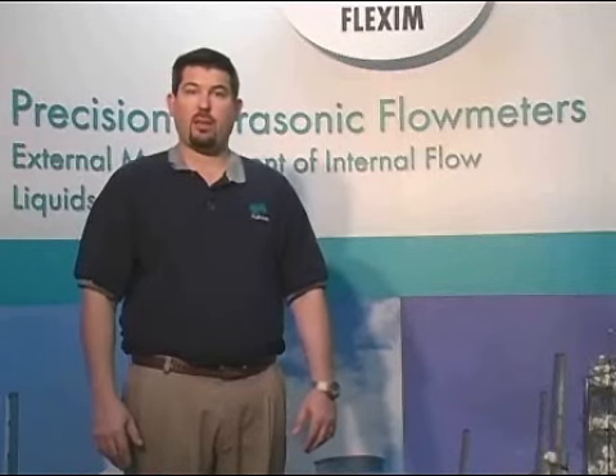Today we covered the basics of how to configure an ADM 7X07 energy meter. We talked about how our temperature probes were installed, how our menu system is laid out, and how to navigate through it. We talked about how to tell the meter what type of fluid and pipe you're measuring on. And then we went into some detail on how to configure process inputs and link temperatures, as well as how to set up outputs like a 4 to 20. After that, we went through the process of actually starting a measurement. And lastly, we talked about how to tell the meter what you'd like to see on the screen while you're measuring, and how to change default values for other functions.